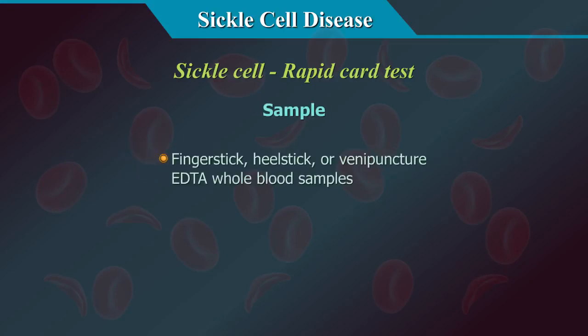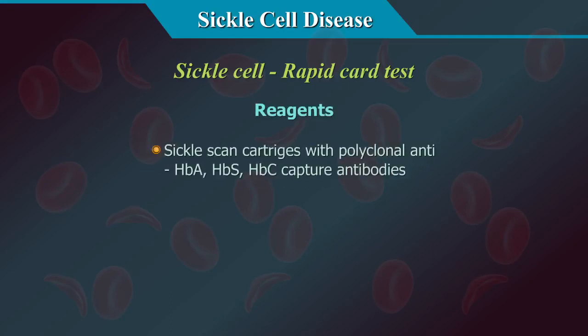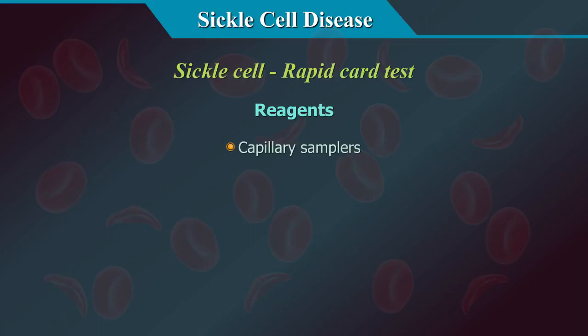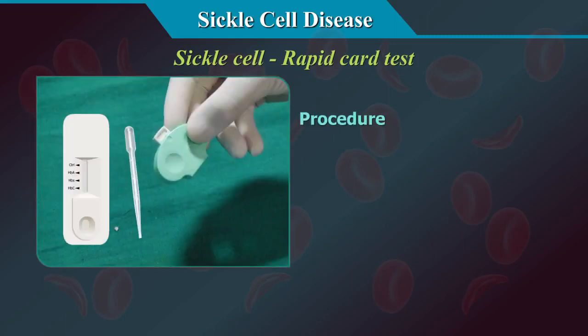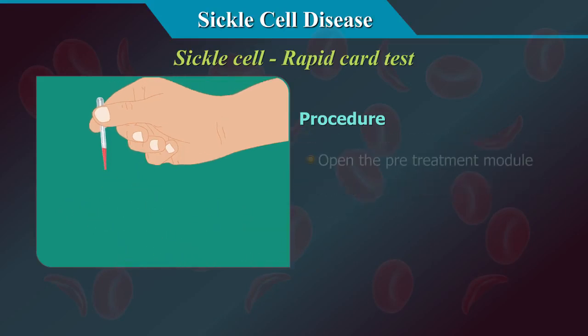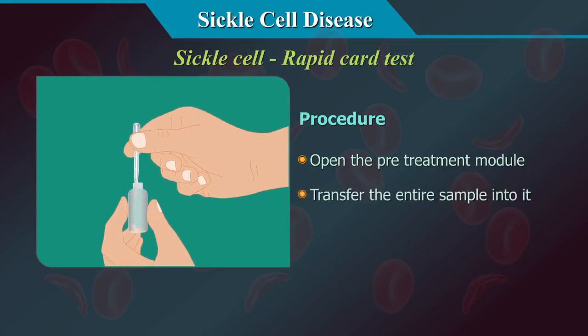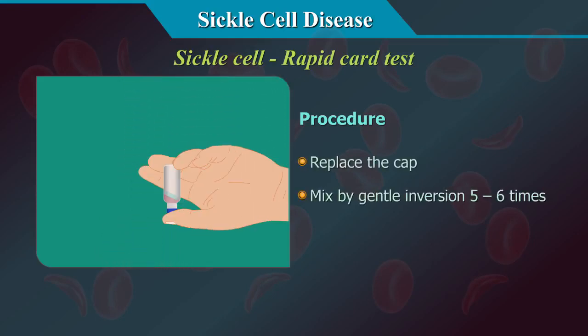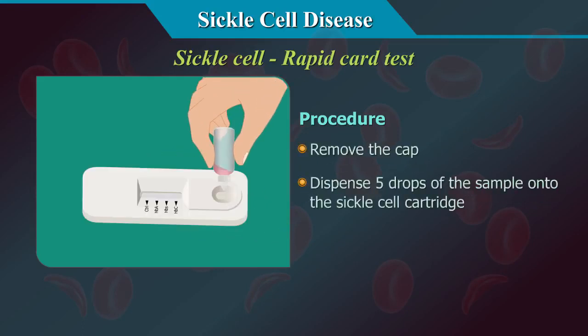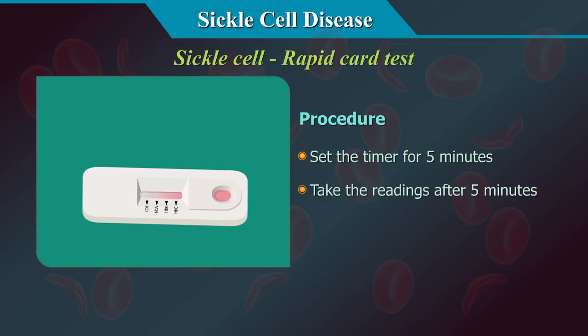Sample types include finger stick, heel stick, or venipuncture EDTA whole blood. Reagents include sickle scan cartridges with polyclonal anti-HBA, HBS, and HBC capture antibodies; pre-treatment modules with buffer; capillary samplers; lancets; and timers. Procedure: open the pouch when ready to use; obtain a finger prick specimen using the lancet aseptically; take 5 µl of blood using the capillary sampler; open the pre-treatment module and transfer the entire sample into it; replace the cap and mix by gentle inversion 5–6 times; remove the cap and dispense 5 drops of the sample onto the sickle cell cartridge; set the timer for 5 minutes and take readings after 5 minutes.